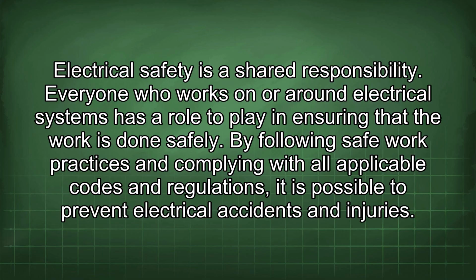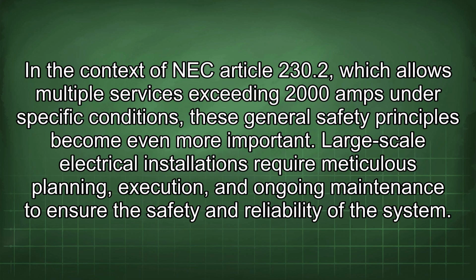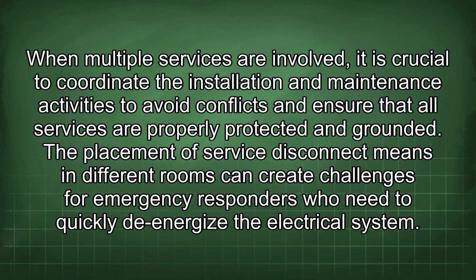accidents and injuries. In the context of NEC Article 230.2, which allows multiple services exceeding 2000 amps under specific conditions, these general safety principles become even more important. Large-scale electrical installations require meticulous planning, execution, and ongoing maintenance to ensure the safety and reliability of the system. When multiple services are involved, it is crucial to coordinate the installation and maintenance activities to avoid conflicts and ensure that all services are properly protected and grounded.